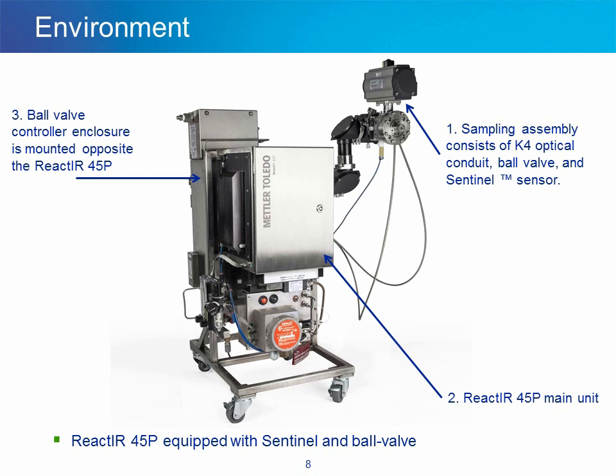For a contemporary system, the setup looks like this. Number 1 is the sampling assembly, which consists of a K4 optical conduit, ball valve, and Sentinel sensor. Number 2 is the React-IR 45P main unit. Number 3 is the ball valve controller enclosure, which is mounted opposite the React-IR 45P. Both can be placed on the same cart and transported, for instance, in a pilot plant application together.